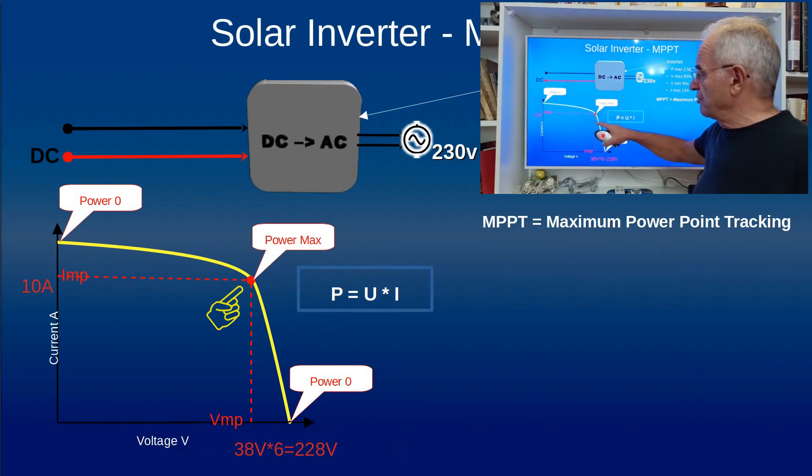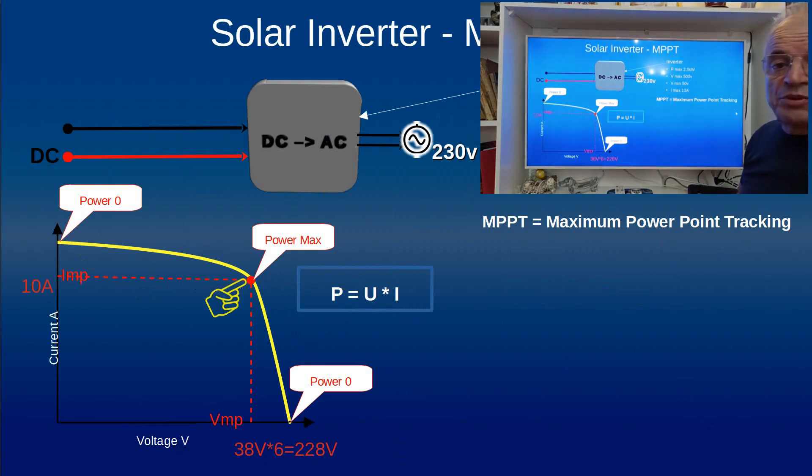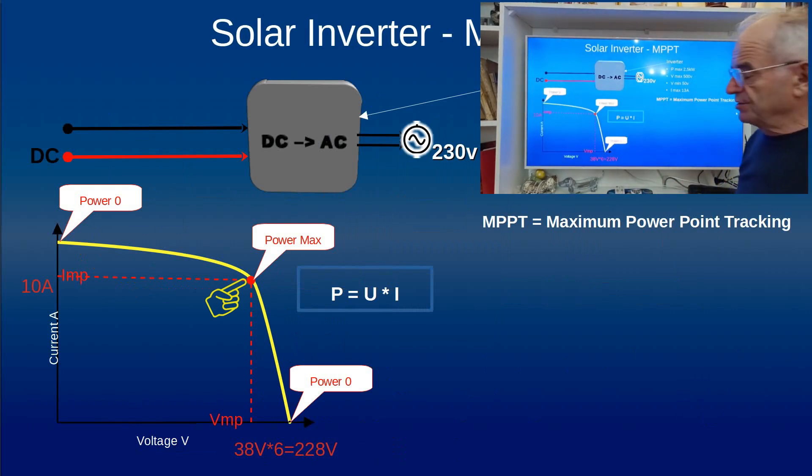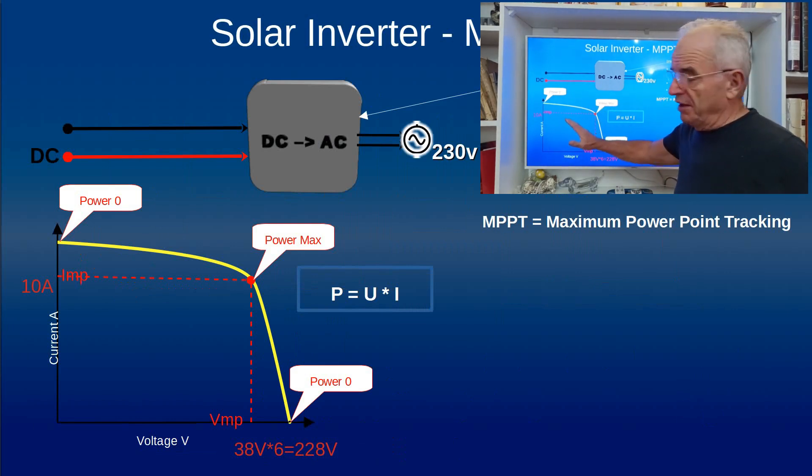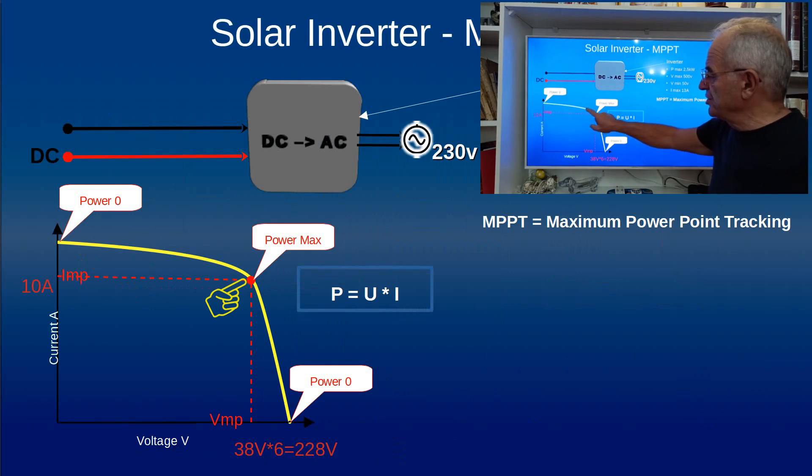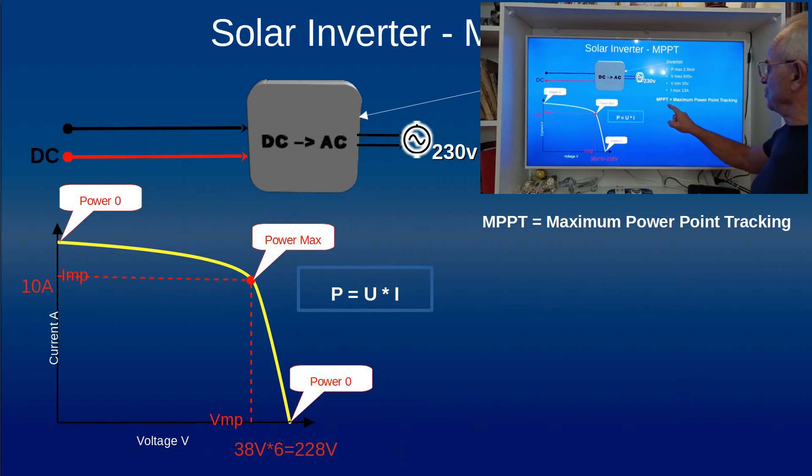But somewhere in the middle there is an optimum for this product where the power is maximum. Here our situation is roughly with a current of 10 amps and a voltage of 38 volts per panel, so in total 228 volts. It's this point which is very important where we have, if we have a lot of sun, the maximum power. Obviously as the sun is reduced, this figure will move on the left. So the purpose of this solar inverter is to track this point.